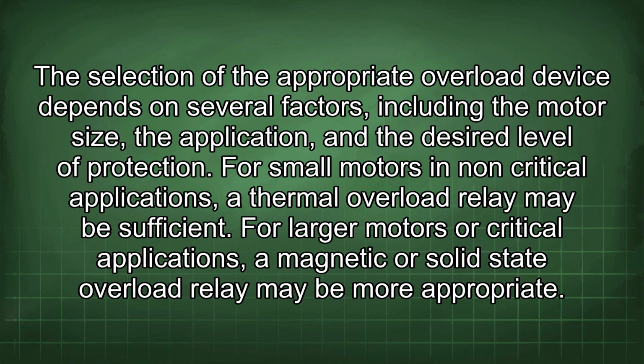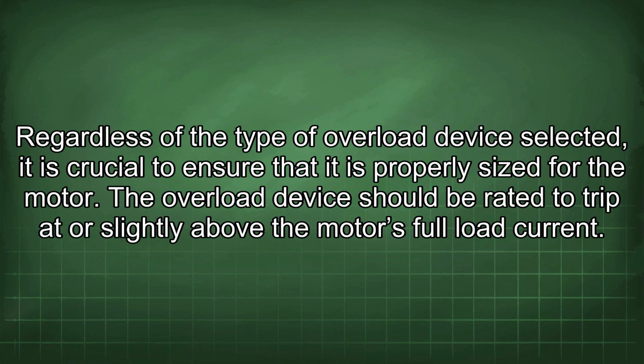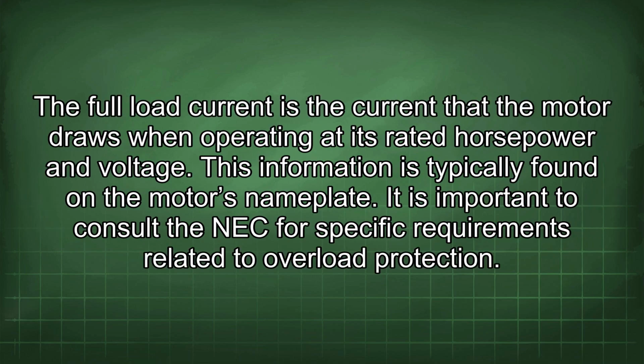The selection of the appropriate overload device depends on several factors, including the motor size, the application, and the desired level of protection. For small motors and non-critical applications, a thermal overload relay may be sufficient. For larger motors or critical applications, a magnetic or solid-state overload relay may be more appropriate. Regardless of the type of overload device selected, it is crucial to ensure that it is properly sized for the motor. The overload device should be rated to trip at or slightly above the motor's full load current. The full load current is the current that the motor draws when operating at its rated horsepower and voltage.